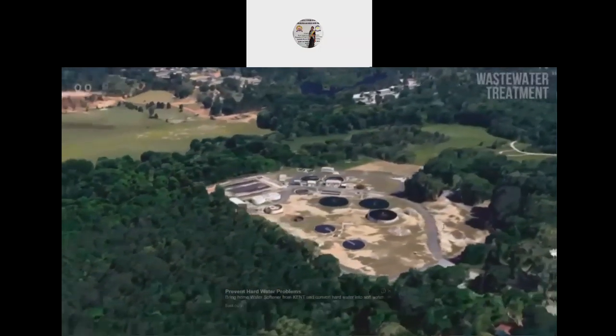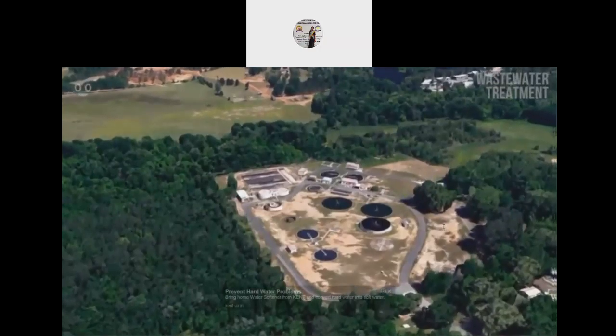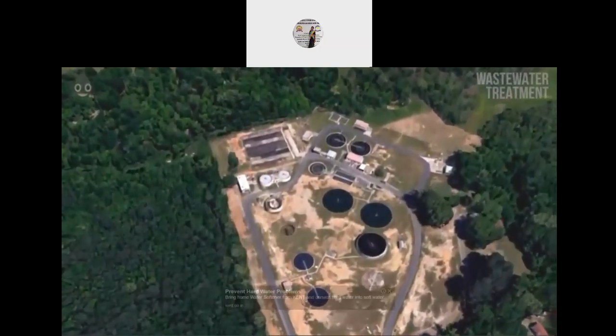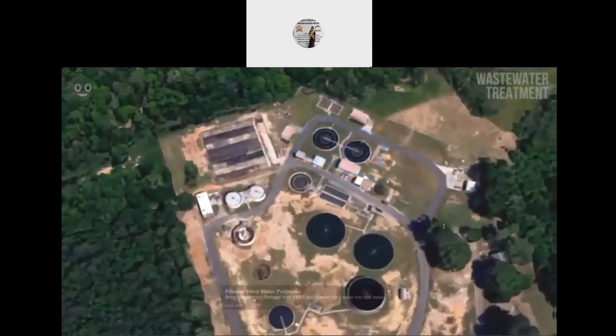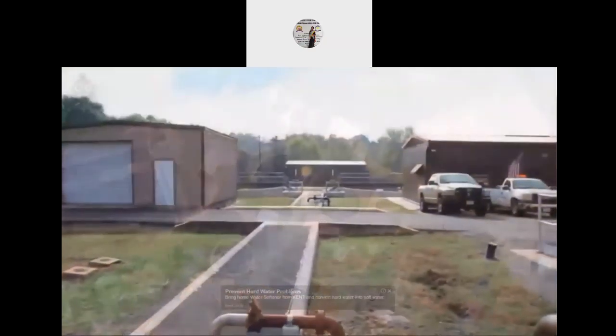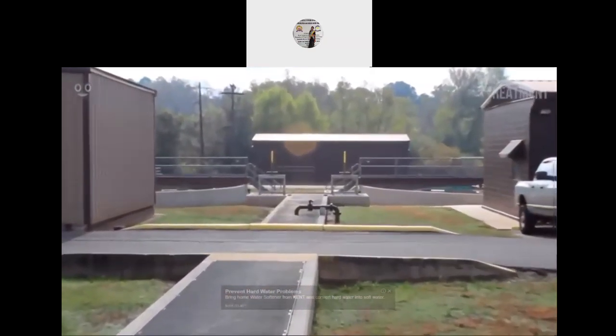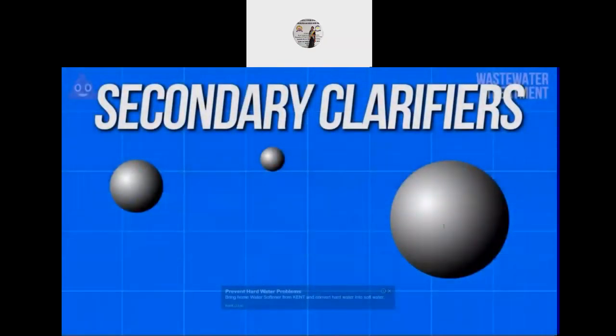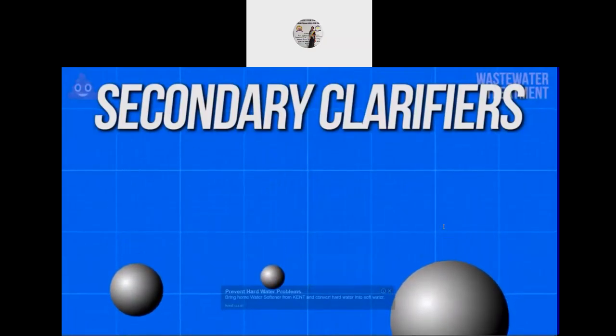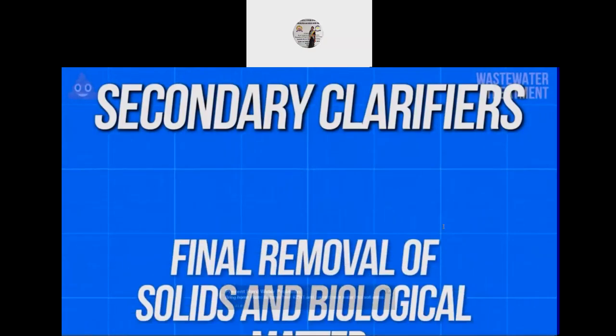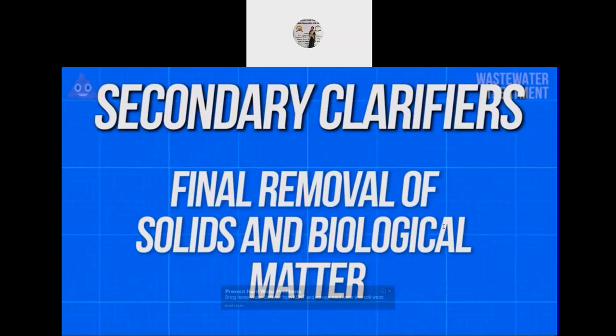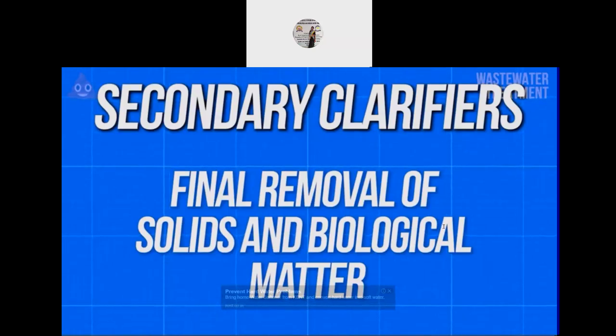Following aeration basins, the effluent along with much of the sludge is pumped into a secondary filter or clarifier, where some of the sludge is removed and pumped back into the aeration basins as the return activated sludge. Further settling of larger particles is also accomplished in these basins, as it is the final step of the process that will remove solids and larger biological matter.